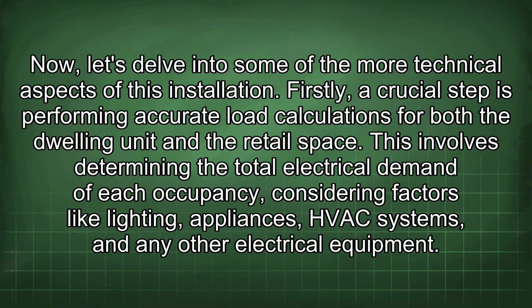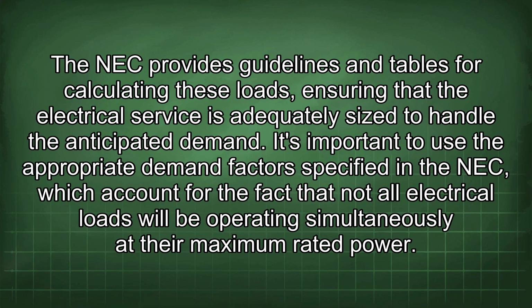Firstly, a crucial step is performing accurate load calculations for both the dwelling unit and the retail space. This involves determining the total electrical demand of each occupancy, considering factors like lighting, appliances, HVAC systems, and any other electrical equipment. The NEC provides guidelines and tables for calculating these loads, ensuring that the electrical service is adequately sized to handle the anticipated demand.